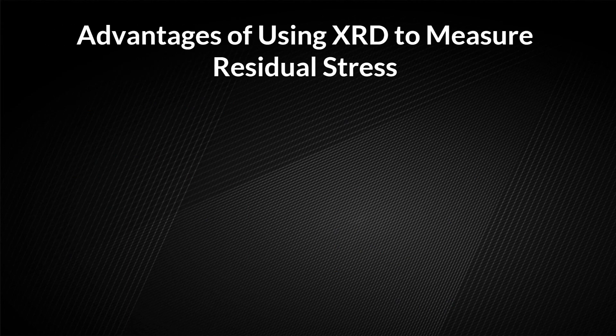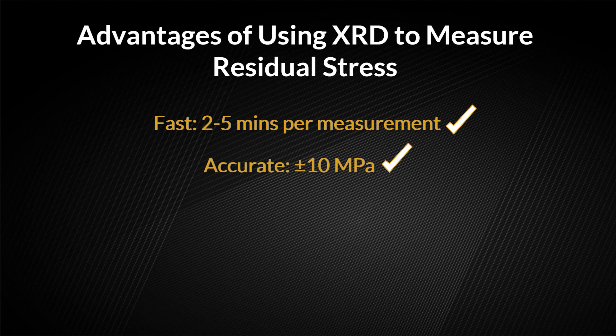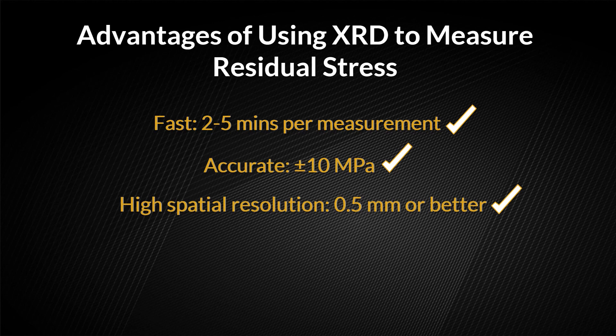There are several advantages of using x-ray diffraction to measure residual stress. It is fast, with most measurements taking 2 to 5 minutes. It is very accurate, typically plus or minus 10 megapascals. Results have a high spatial resolution, typically 0.5 millimeters or better.